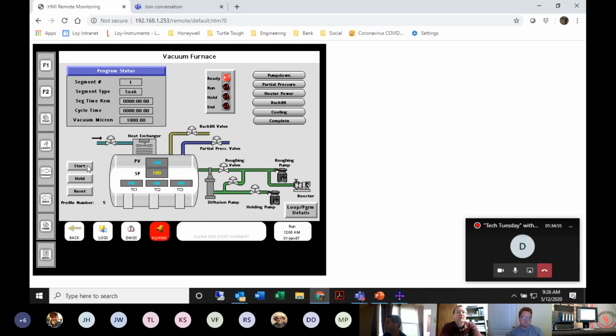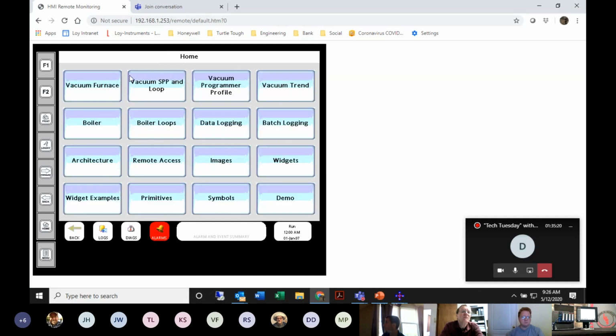So right now I do have a set point programmer loaded into this. I'm going to go ahead and hit start. And you actually will see now we're in the pump down sequence. So the pump down sequence, all of this area over here is now green. It's pumping down. And once it gets down to a pump down level, then we're going to start ramping our temperatures up. But as we wait for that, let's go ahead and move on to another display and show you some other displays that allow you some different visuals into the process.